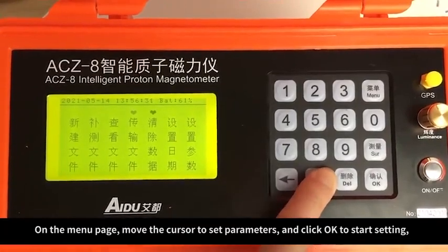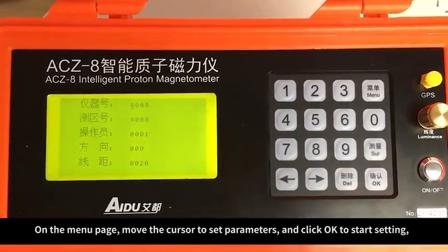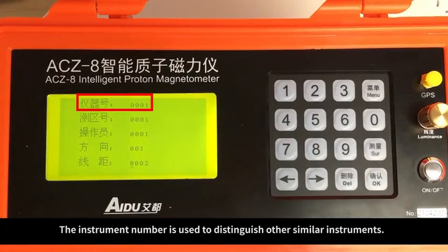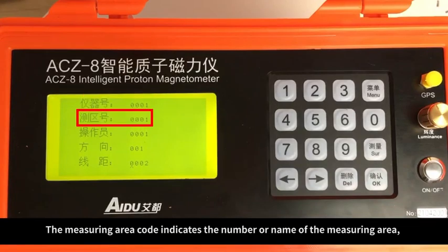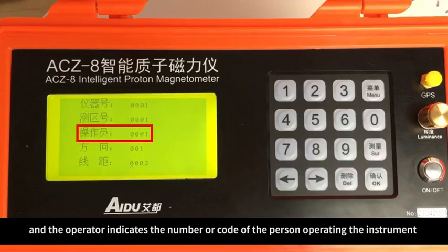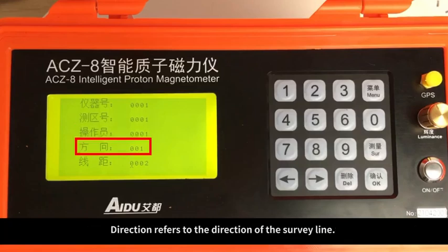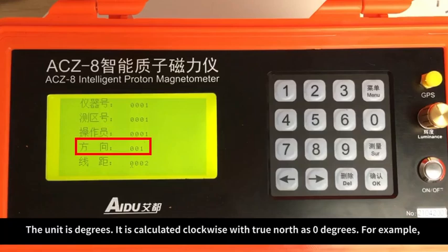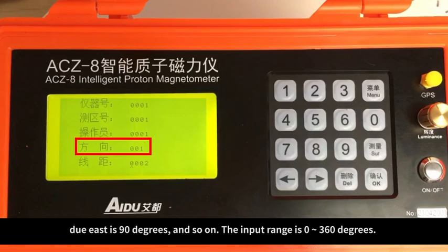On the menu page, move the cursor to set parameters and click OK to start setting. The instrument number is used to distinguish other similar instruments. The measuring area code indicates the number or name of the measuring area, and the operator indicates the number or code of the person operating the instrument. Direction refers to the direction of the survey line. The unit is degrees. It is calculated clockwise with true north as 0 degrees. For example, due east is 90 degrees, and so on. The input range is 0 to 360 degrees.